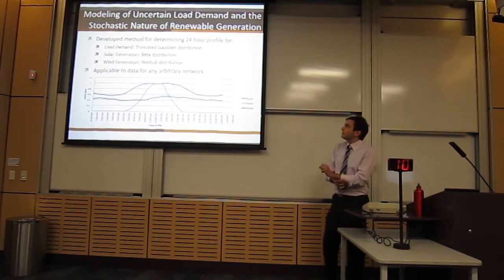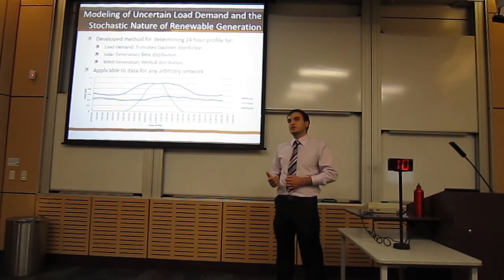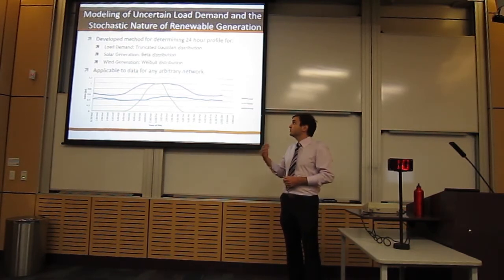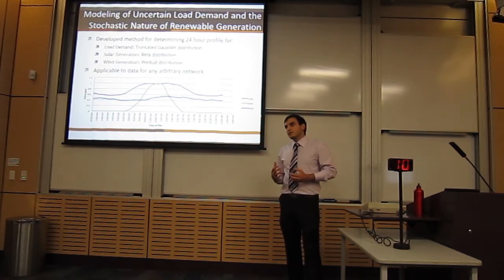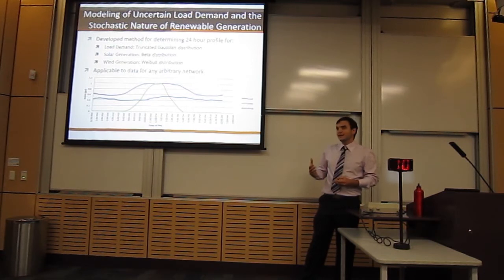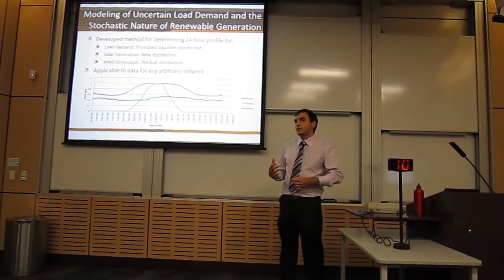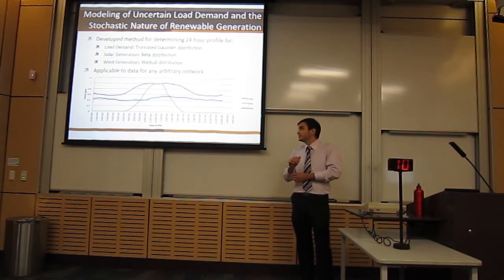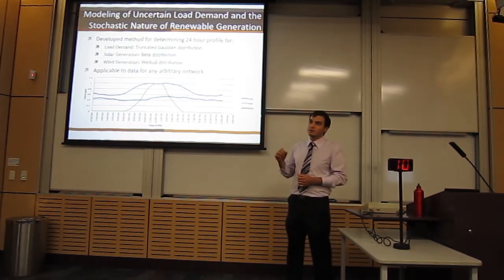To model the uncertain load demand and stochastic nature of renewable generation, I've developed a method for determining typical 24-hour generation profiles using distribution functions for each of the three profiles. For renewable generation, you cannot account for periods such as cloud cover reducing solar output. However, I've proposed a method to develop a typical 24-hour profile consistent over the duration of a year, ignoring these small inconsistencies. This method is applicable for data from any arbitrary network, rather than being developed for a specific single network.